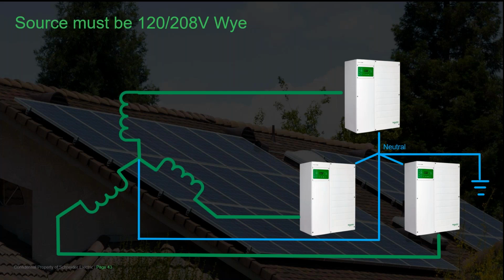The XW Pro 3-phase configuration requires an ABC rotation from the source. The XW Pro system will report an event code F70 if the rotation is reversed coming from the 3-phase AC source. In lieu of rewiring, it is possible to assign XW Pro number 2 as phase 3 and XW Pro number 3 as phase 2.